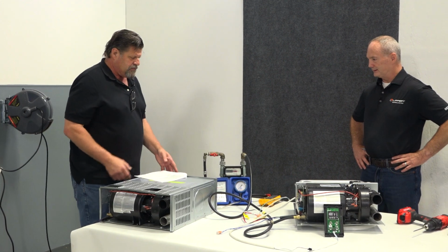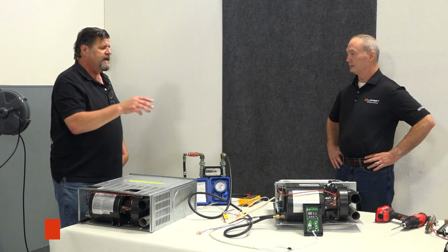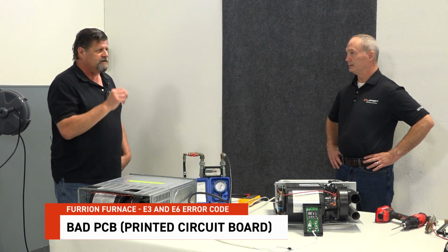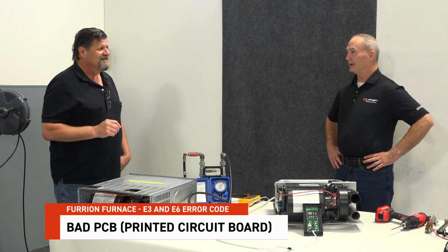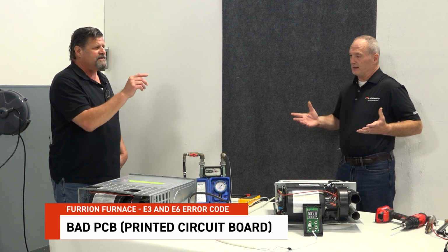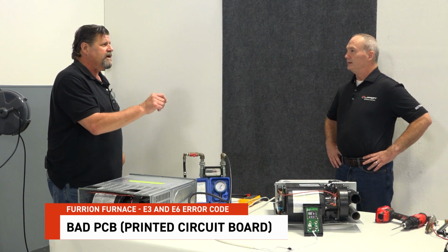Now the next thing on the list would be the E3 fault code. E3 and E6 are more board issues, but it's dealing with how the board is sensing the gas valve. And that's electronics that's just a little bit over my head. Yeah. Because it's not just reading the circuit. Because if I have a bad coil, I won't get an E3. I'll just get no ignition.